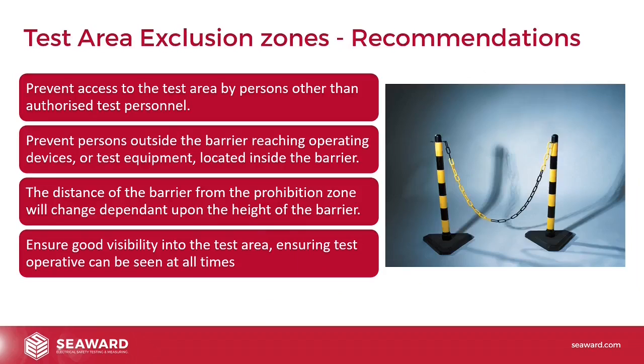Test area exclusion zones. These prevent access to the test area by persons other than the authorized test personnel. They also prevent persons outside the barrier reaching the operating devices, the test equipment, or anything located inside the barrier. So that's really important. So we want to try and keep untrained people out using these barriers, but we also want to make sure they can't reach in and touch anything from outside those barriers. So the distance between the barrier and the prohibition zone will change depending on the height of the barrier. So if you have a 3-foot barrier, it needs to be a little further away from the prohibition zone to stop people reaching over it. If you have a 5 or 6 foot barrier, it can be a lot closer because they can't reach over and touch the operator or the equipment or the device under test.